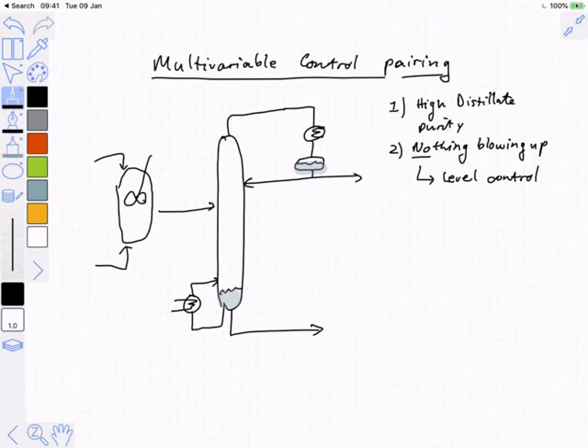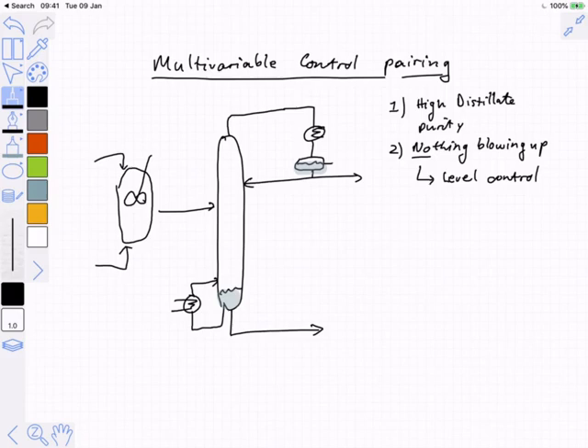There are a whole lot of sub-goals around not killing anybody — many of them are inventory control problems. There's got to be a lot of levels controlled, and to control something I need to measure it. I can't claim to have level control if I don't know what the level is. So I need at least one level transmitter here, and at least another one over there if I want to control those things.